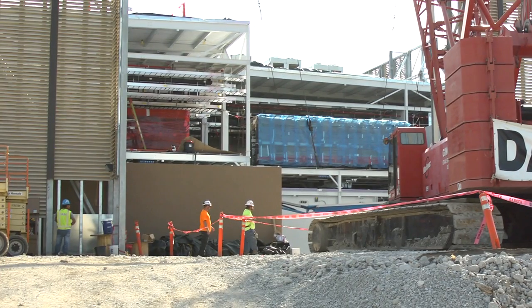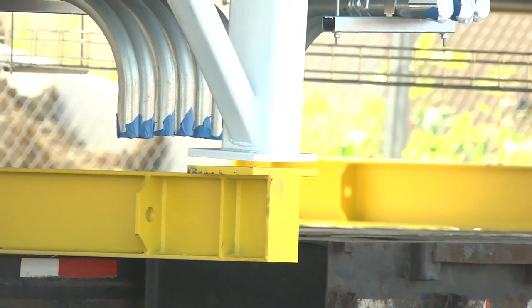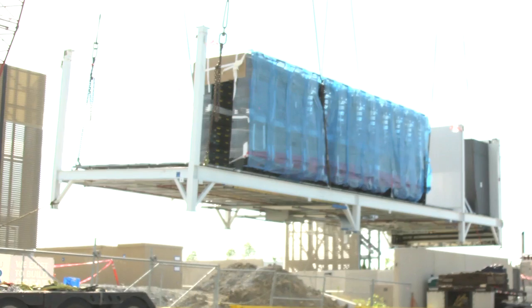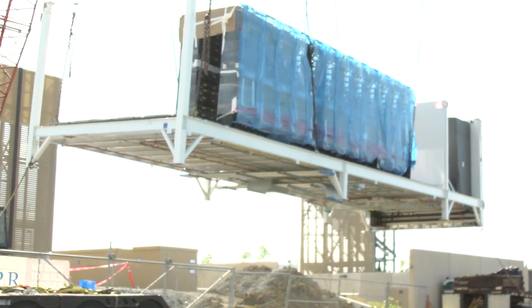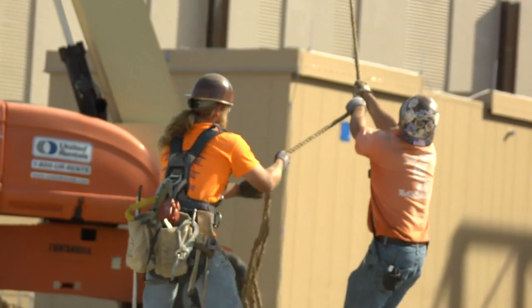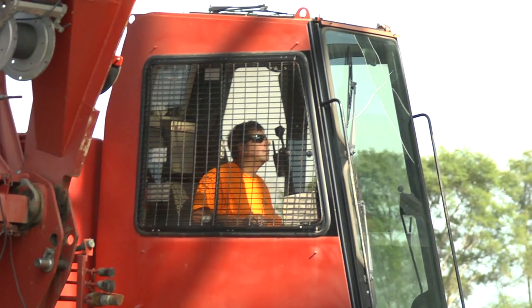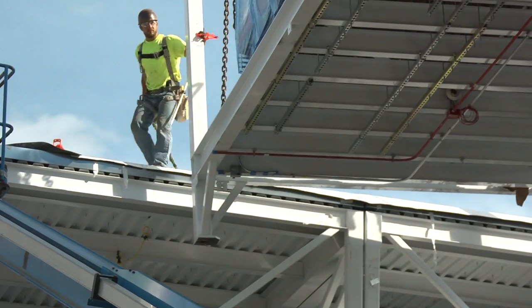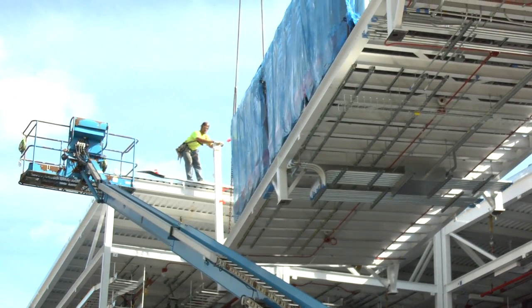What we're seeing over here with the crane — the crane is a Manitowoc 999 Series 3, 275-ton crawler. The modular units weigh anywhere between 16 and 35 tons depending on the equipment loaded within them. Within each unit, all equipment is pre-installed at the factory, then on-site the units are bolted together, connected, made watertight, roofed, and the facility is ready to go.